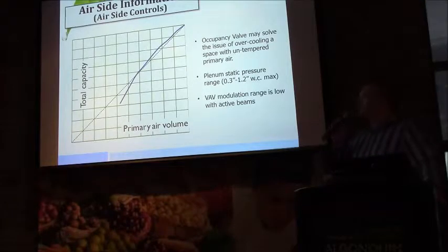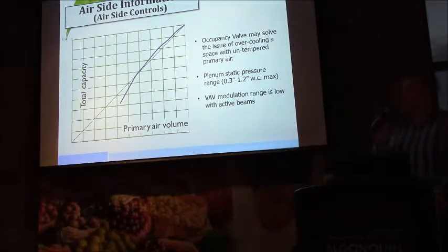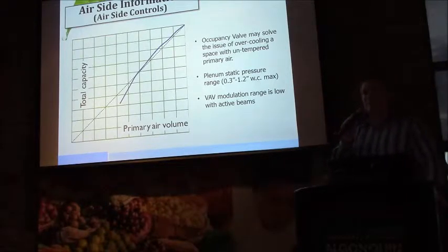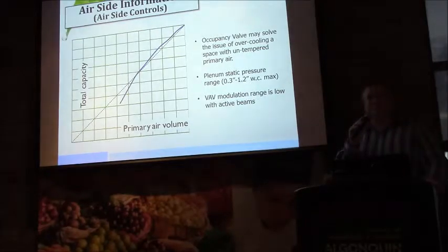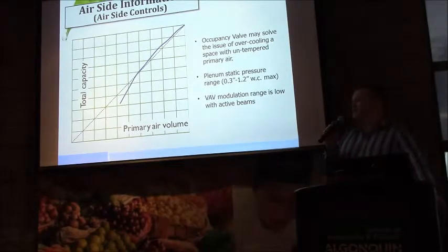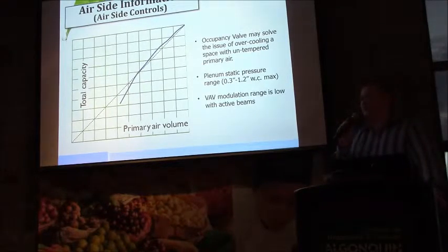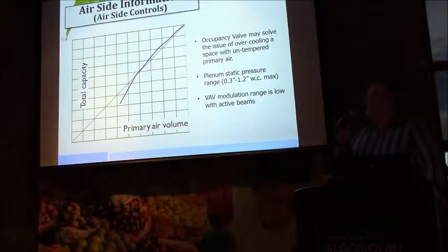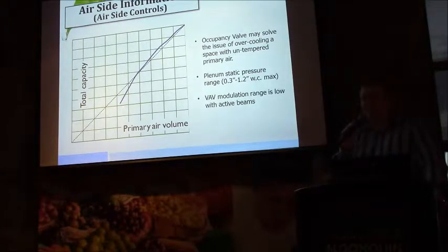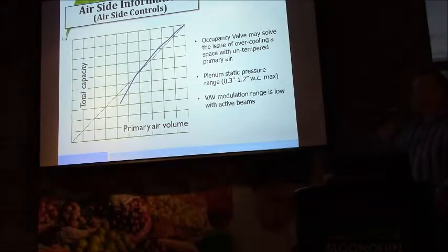But ultimately, the usefulness of VAV or occupancy valves comes into play when we look at the risk of overcooling a space. So earlier when we talked about the percentage of primary air that's delivered to the space that can be used as a credit to reduce the total sensible cooling in the room, that plays against us in a more highly occupied space because the volume of air is now closer to delivering the total cooling capacity. And without a load, if that is representative of 50% of the total cooling effect of the space, we're going to overcool the room. And so a two-position or an occupancy valve makes a lot of sense, although it creates some other issues relative to balancing our plenum static pressure upstream for the other beams in the array. There are means to address that.